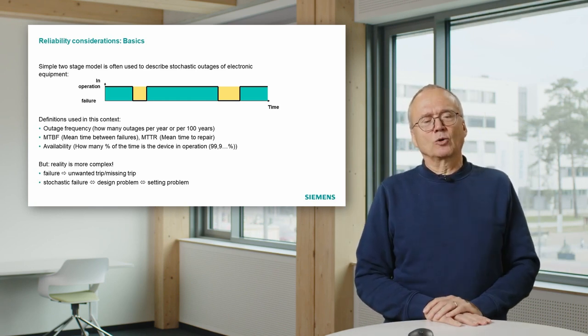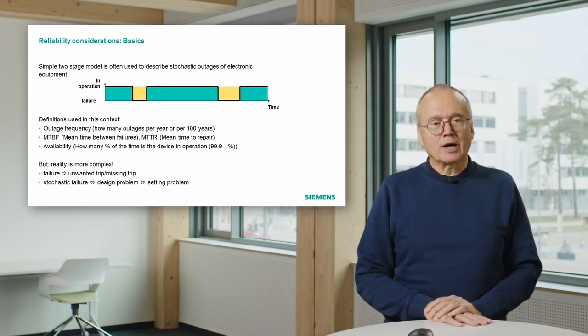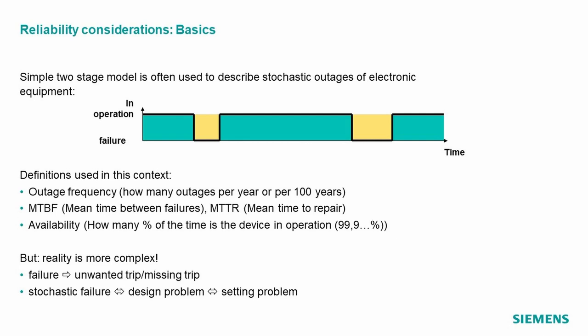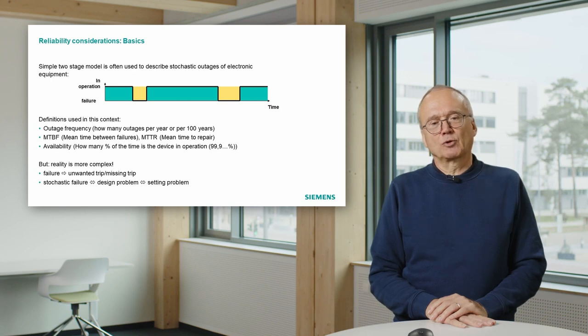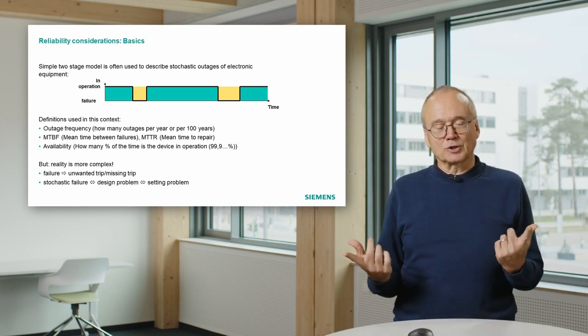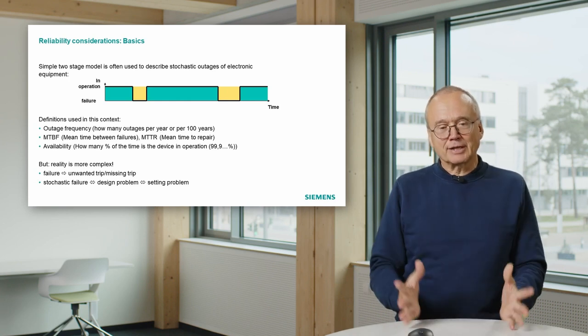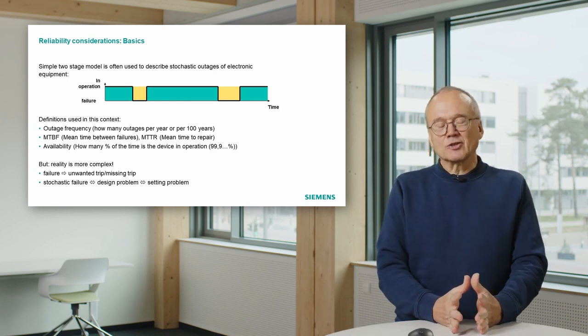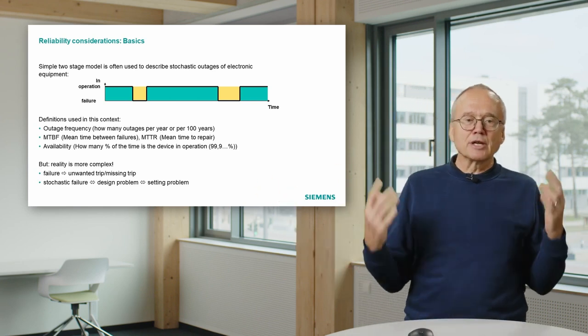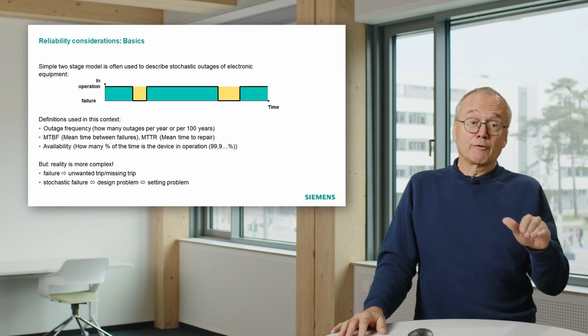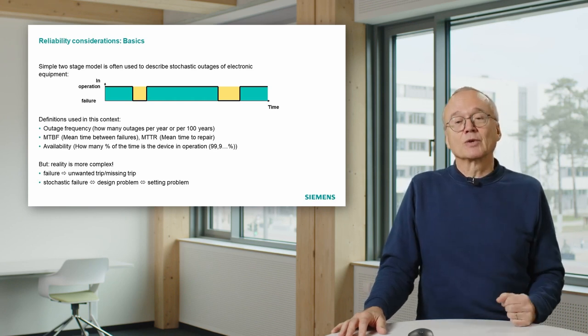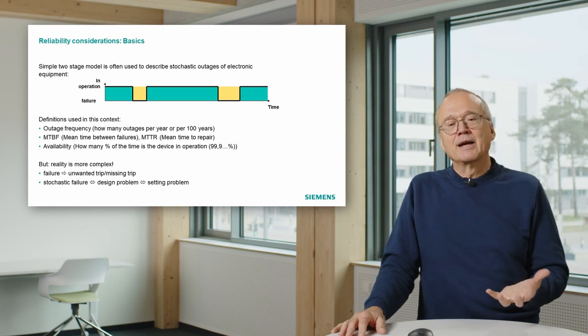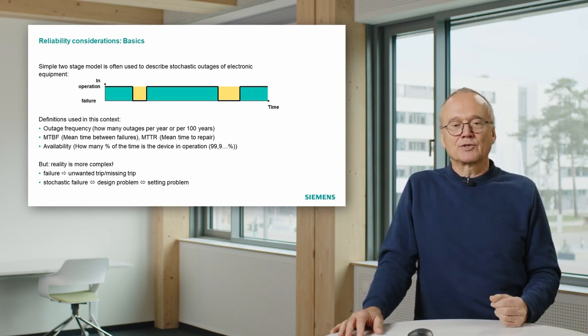This diagram and also these quantities refer to stochastic failures. If I remember the type of failures I had to deal with during my active time, the majority were not the results of stochastic failures. The majority were results of design problems or setting problems. And those are not stochastic things. For instance, if you have a protection concept where somebody did a wrong design because a signal was misinterpreted, or we even have a software bug in the protection relay, it's not a stochastic thing. It's always there and it shows up in a dedicated situation.